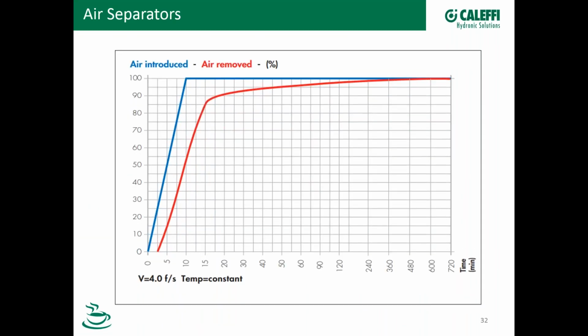Here's a graph that comes up a lot. We get a lot of questions: what's the efficiency, or what is the specification for your air separators? And this is an actual test graph, based on empirical data from testing we did at one of our labs. This blue line here, you can see we introduced a certain amount of air within 10 minutes. On the bottom here, is that 7.5? No, that's 10 minutes. So we introduced some air, and then we measured with a mass flow meter the air being removed as it was introduced.